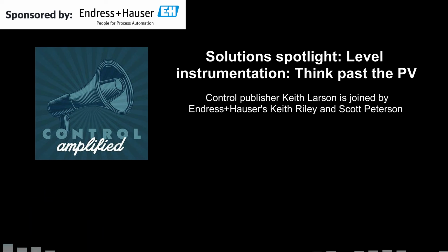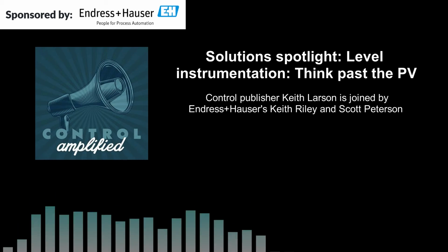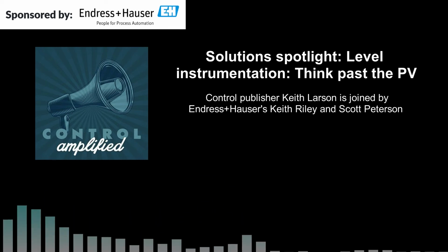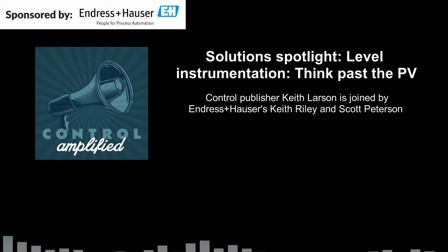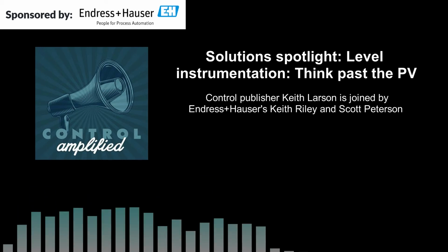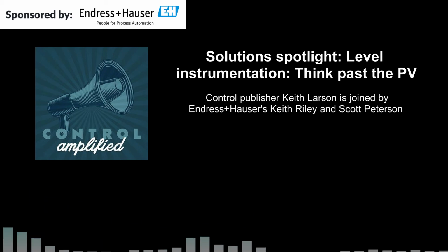All right, Keith. Well, that usually falls into one of three areas, which I'll state here first. One is the diagnostics, one is verification, and one is monitoring or predictive maintenance. Scott already touched a bit on the diagnostics. There's better diagnostics. A typical scenario in the past would have been you're using your 4 to 20 signal. You get an alarm warning back at the control system. You have to send out a technician to go find the instrument that's sending that warning, find out what the diagnostic code on that is. Then you're radioing back to the control system.